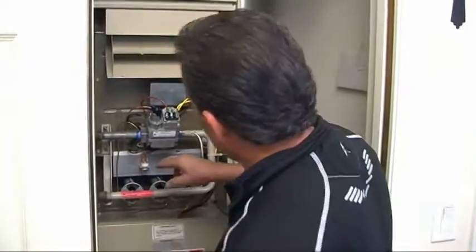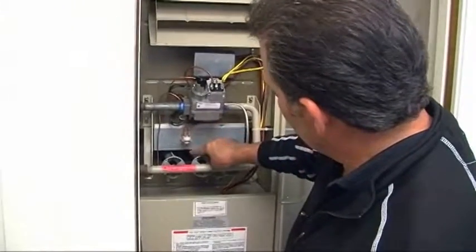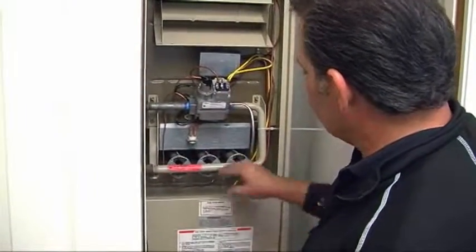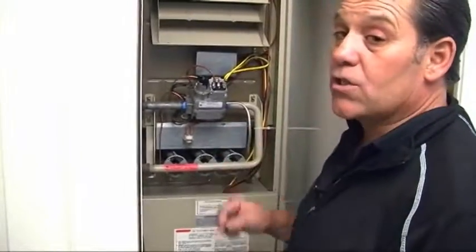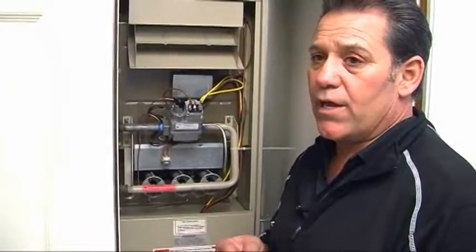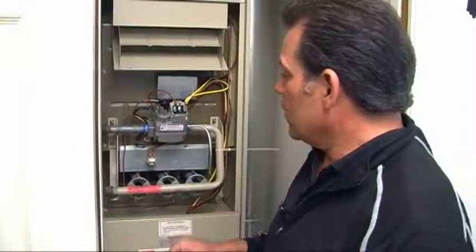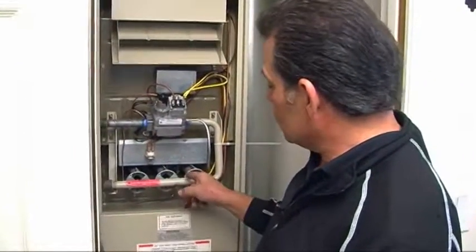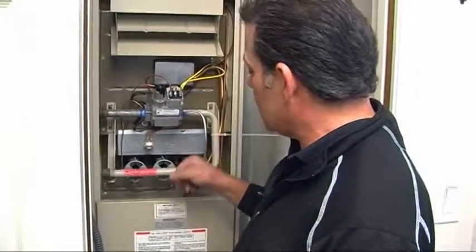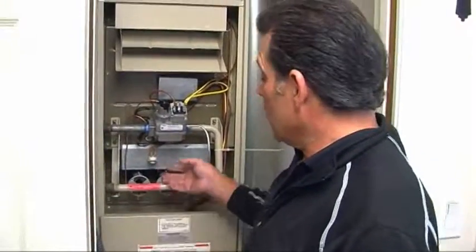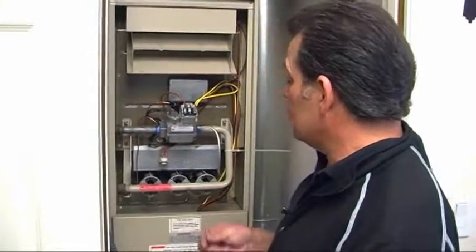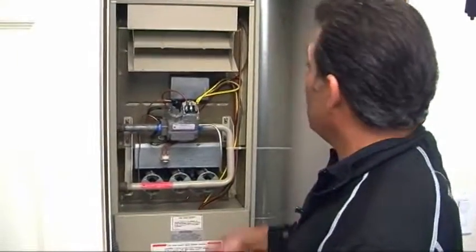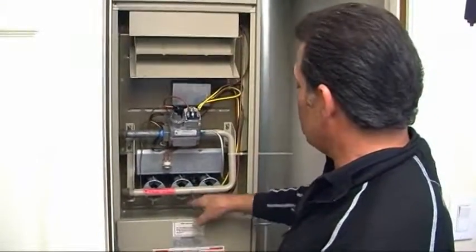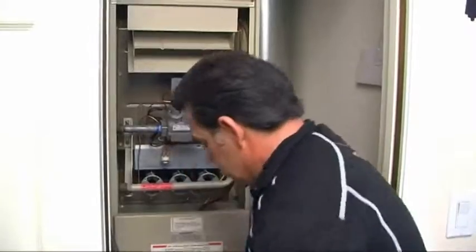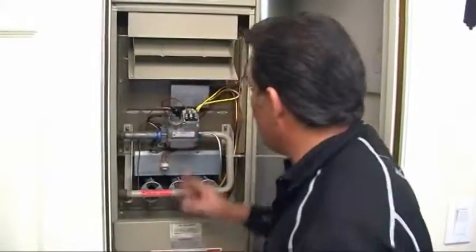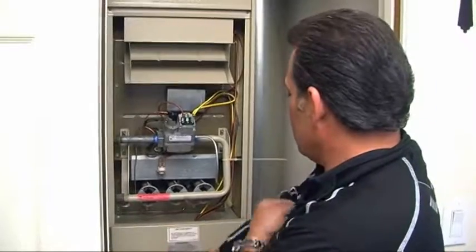From here, we run down to our flame rollout switch. This is a one-time fuse rollout switch. If the flame does roll out from the heat exchanger, it's looking for oxygen. In order to create combustion and to keep combustion, you need three things. You need a fuel source. We have that. We have an ignition source. We have our pilot lit with the thermocouple keeping it lit, and then you need oxygen. So if you ever have to replace this switch, you know that you have a problem with either your combustion air not getting into this area here and into the burner chamber through the grills, or there's something blocked in the vent which is keeping it from creating combustion.